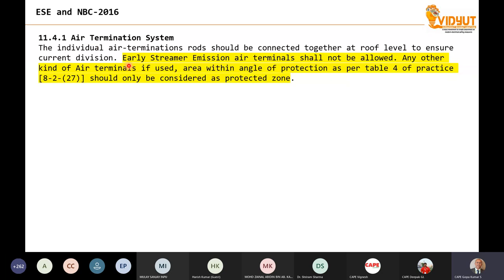Air termination system. The draft says early streamer emission air terminals shall not be allowed. Any other kind of air terminal, if used, the area within the angle of protection as per table 4 of the practice shall be considered as protected zone. So indirectly, what it says is, if you have a rod for lightning protection, we are supposed to consider that the area within the angle of protection is the protected place. So even if you use an ESE rod, you should consider the angle of protection and use it. This is the recommendation in the draft.